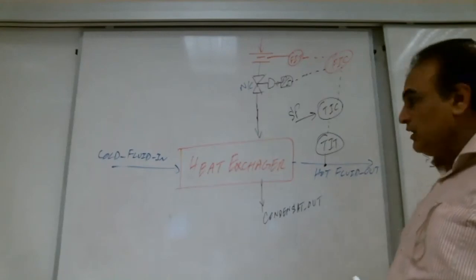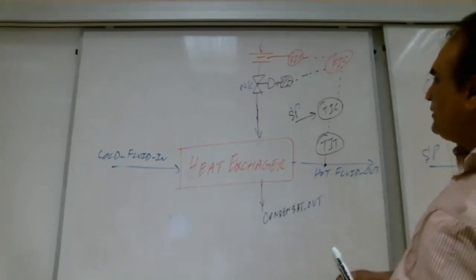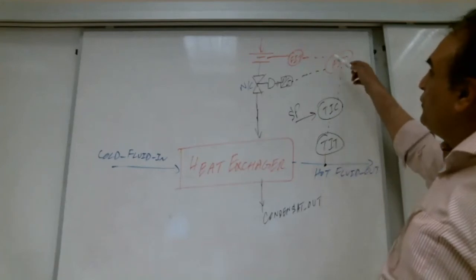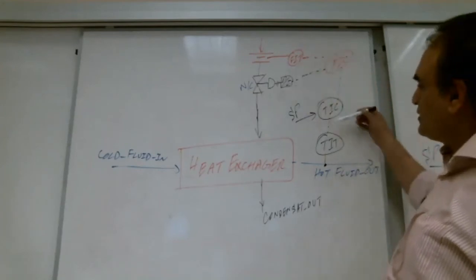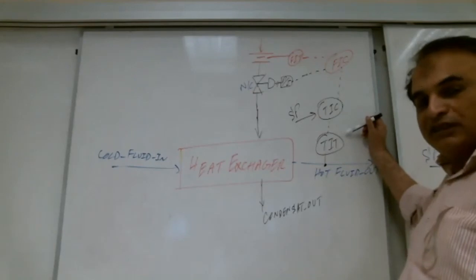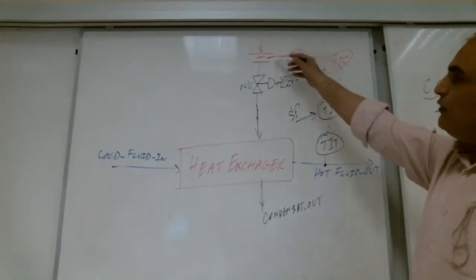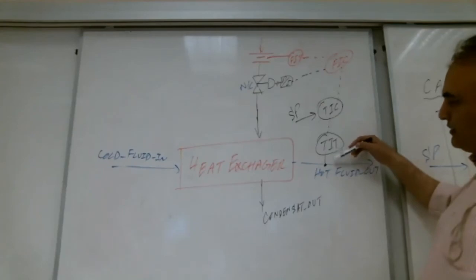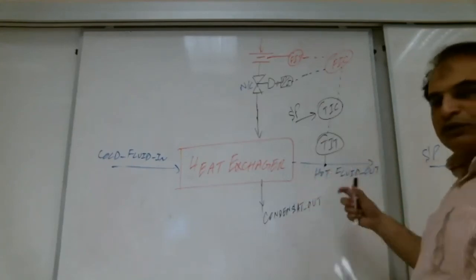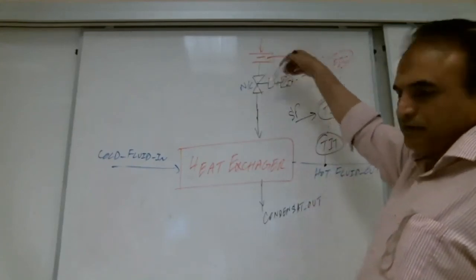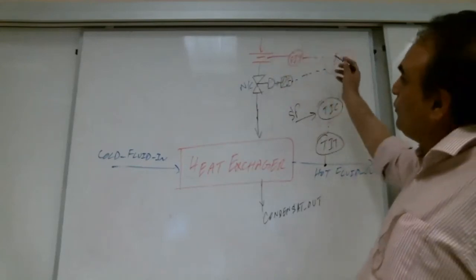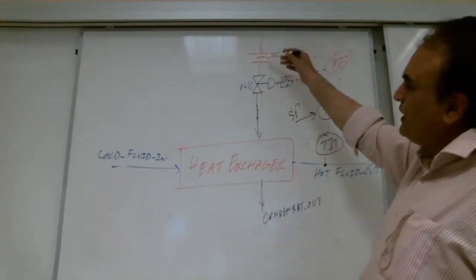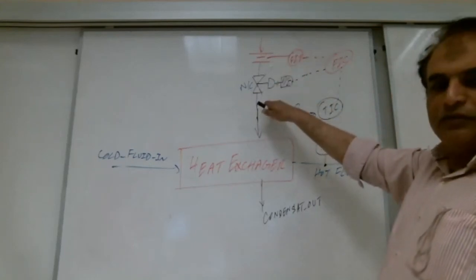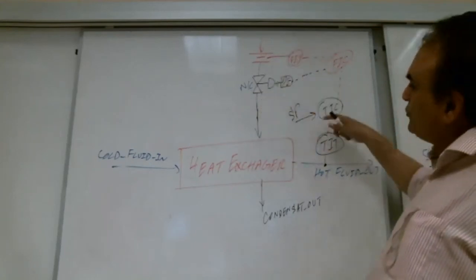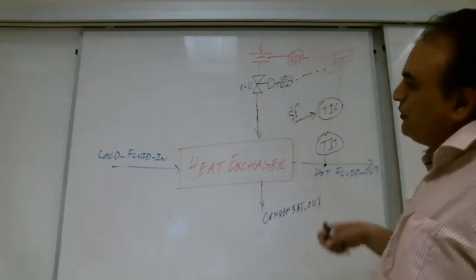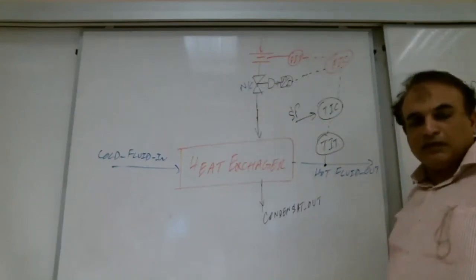So right away this controller will know this is broken. This is one thing. And the other thing was there that it was far slower. So now this action is not just depending upon the temperature. No, this action is also depending upon the flow. So as soon as the temperature lag time is more, this controller will increase the flow also. Before there was no control on the flow. Now it is also reading the flow. If flow is less, no need to open the valve more. If the flow is more, then open the valve more. So the lag time will be reduced. So work with me, and a lot of other things.